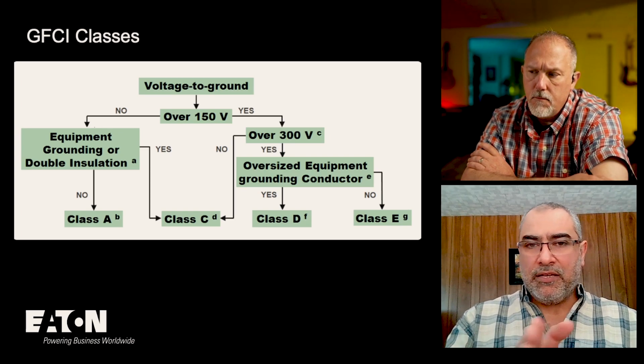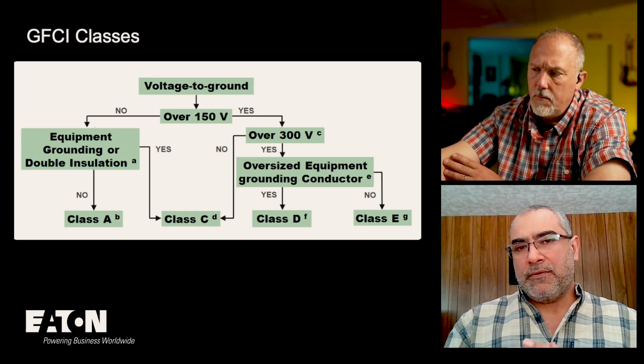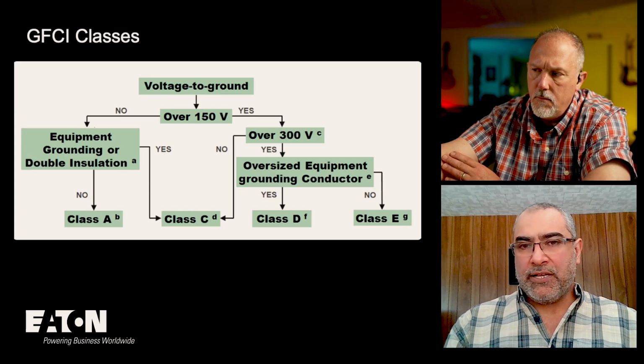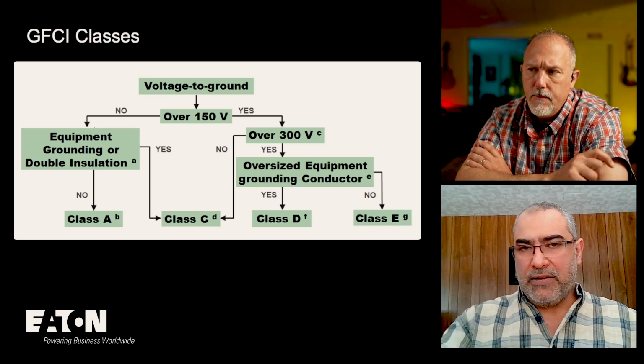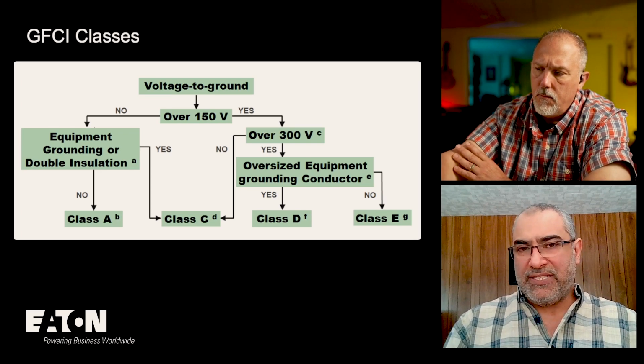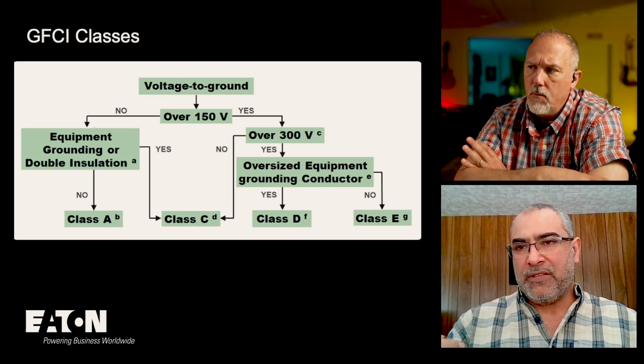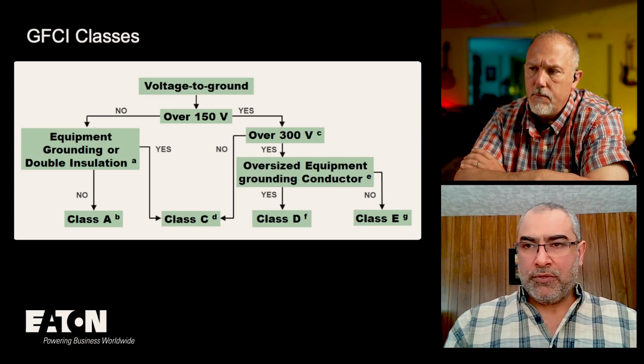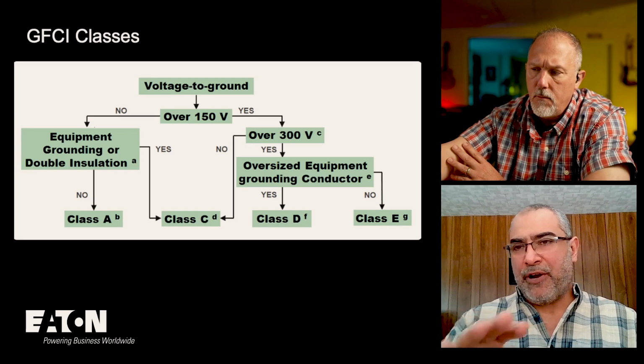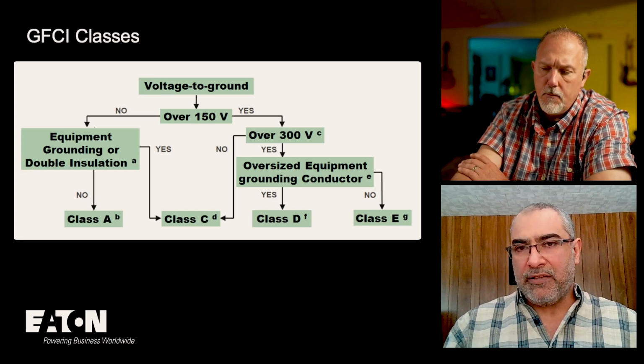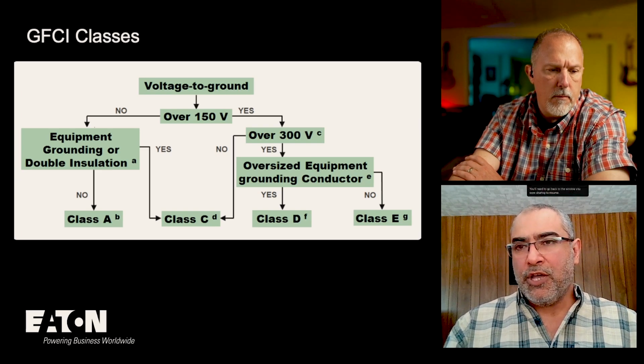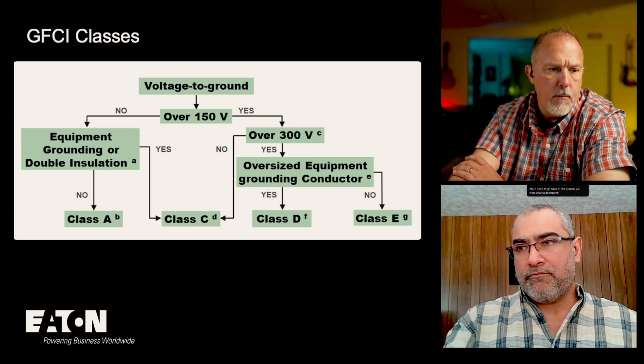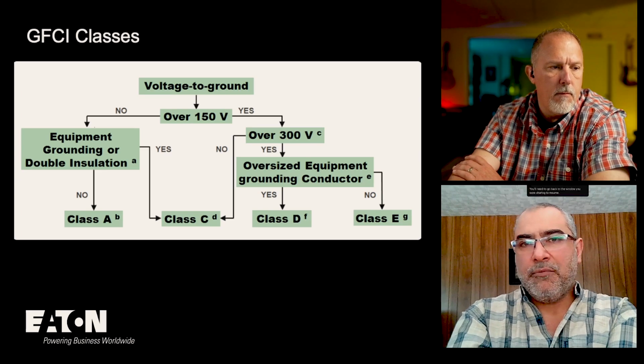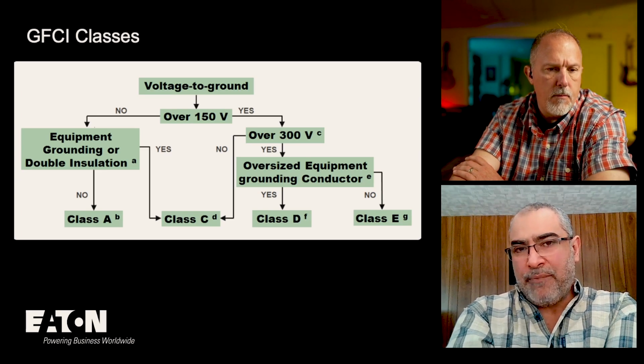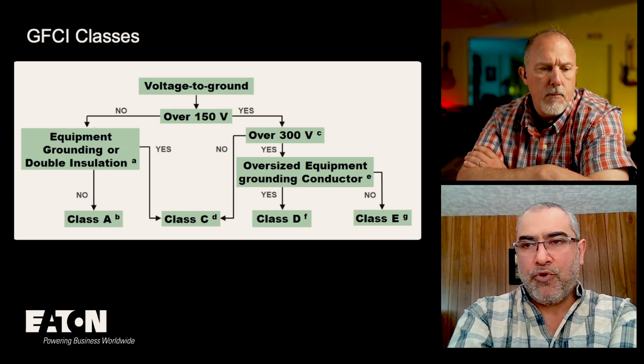It's a concept. But then the Class D you can use, assuming that your equipment grounding conductor is oversized, and in one of the appendices in UL 943C, it shows you how to do it. The whole point is they're trying to limit the voltage across the body to 150 volts or less. So it's like a parallel path; the idea is to make sure that your equipment grounding conductor is oversized so that most of the current bypasses the person and goes through the equipment grounding conductor back to the source. But for most practical cases in the US, it will be Class C. That will be the more dominant.